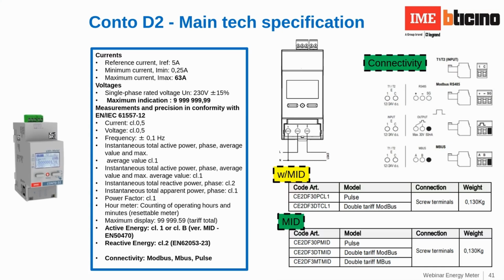So let's see more in detail the Conto D2, which is our single-phase energy meter. Current and voltage are in class 0.5. Active energy is in class 1 for the non-MID version, and in class B for the MID version. The neutral connector has the same size of the voltage connector, so you can use the same cable for the phases and for the neutral. In the upper part of the slide, you find the connector for the Modbus and M-Bus communication protocols, and the pulse input and output, depending clearly on the model that you choose. For example, if you choose the item number CE2DF30PCL1, you have only the pulse output and the pulse input, or the tariff change. Depends how you want to use this input, for pulse or for tariff. You have the alternative.